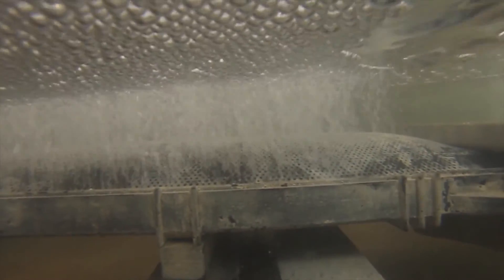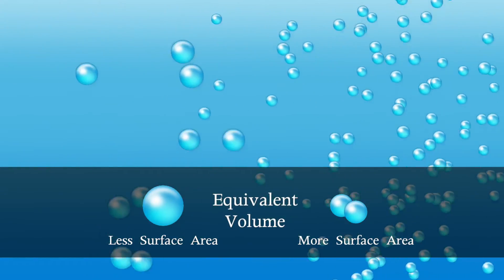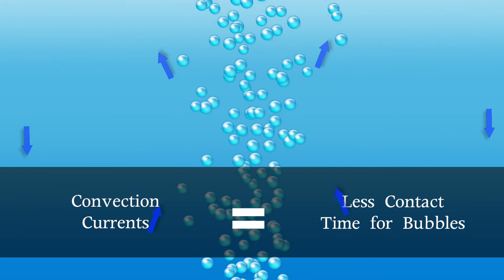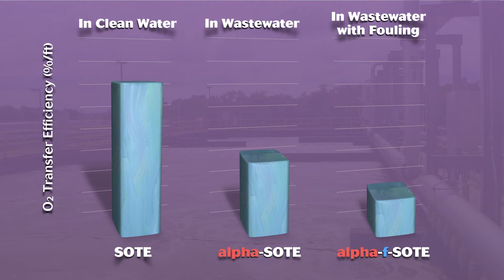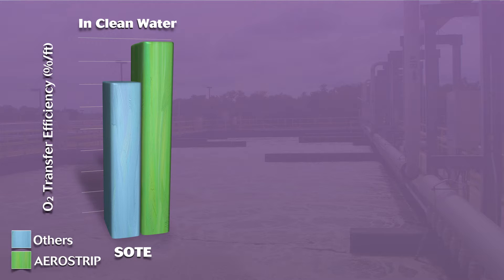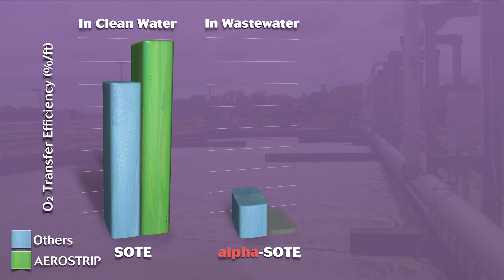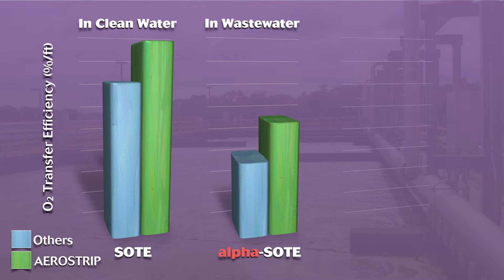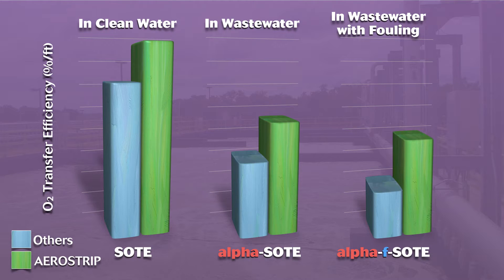Additionally, when diffuser pores start to plug, air is directed unevenly to other diffusers, which increases bubble size and increases convection currents in the basin. Aeration efficiency then begins to drop like a rock. This is common with unmaintained EPDM diffuser systems, particularly when operating at the low flux rates needed for energy efficiency.